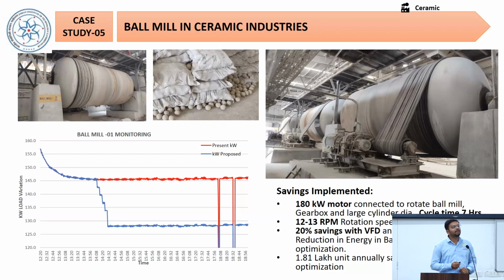So we identified that the industry has already implemented a VFD in the system, but they are using it at the same frequency. We monitored throughout the 7-hour cycle, and we observed that after the initial 110 to 120 minutes, a significant energy consumption reduction is achieved in this ball mill pattern. So we took a trial to reduce the frequency, because the motor is rated at 1400 RPM. We reduced the frequency to 45 and 40 hertz, and we took the trial and saw the difference in the ball mill rotation.